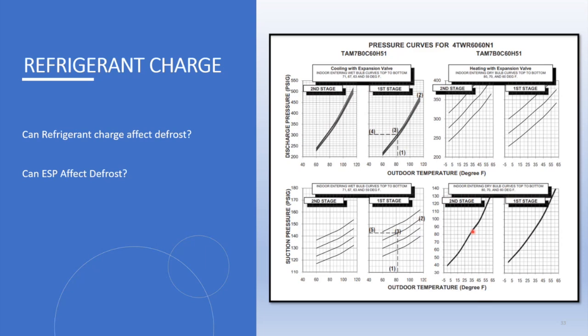But if these pressures match what you have in the charts, I would probably move on. But if they don't, you can't adjust charge based on these pressures. These are just for reference only. The only way that you can charge in heating mode when it's below 55 outside is weigh in and weigh out, and come back in the spring and adjust via subcool.